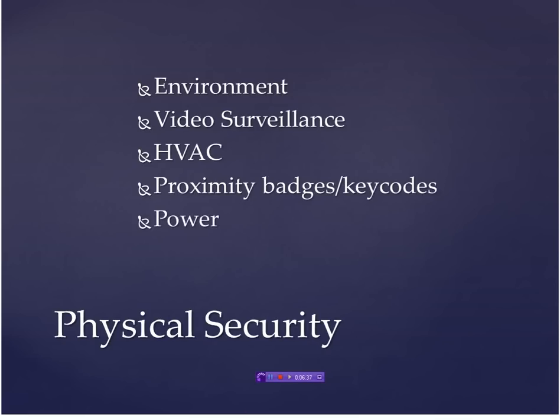Regarding power — the data center is N+1 and the facility is N+2. The data center is fed off emergency power and has its own dedicated transfer switch that controls input feeds. The switch is fed by normal power with N+2 generator backups. These generators also supply the rest of the hospital for emergency power — they are diesel-powered with a 100-gallon underground tank. Just a couple weeks ago Northwest Energy had a transformer go out and we failed over to the first generator. The system was intelligent enough to realize that wasn't enough power and the second generator kicked on. The data center has two power zones if both generators fail.